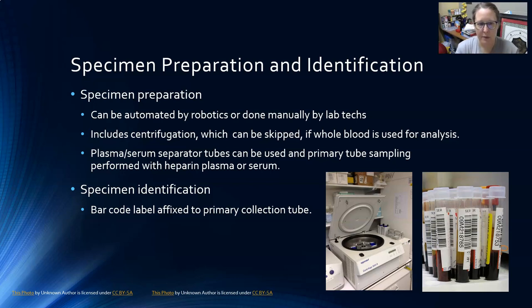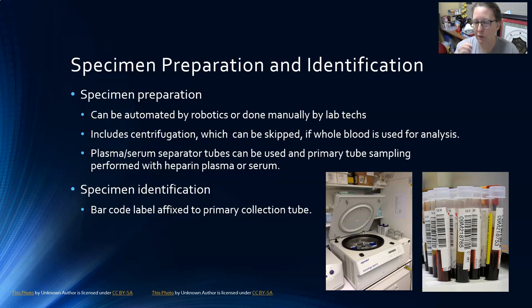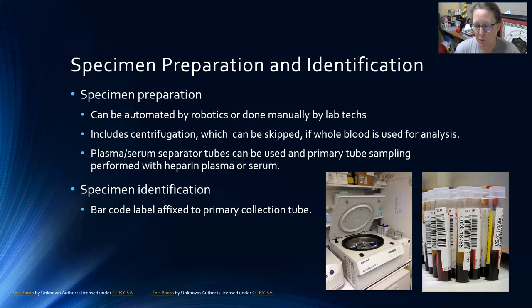Plasma or serum separator tubes can be used, and then primary tube sampling can be performed, meaning there's no need to pull specimen off of the primary tube — it can just be uncapped and loaded straight onto the analyzer. Primary tube sampling on the analyzer will be done with either the heparin plasma or the serum, depending on what the sample was.